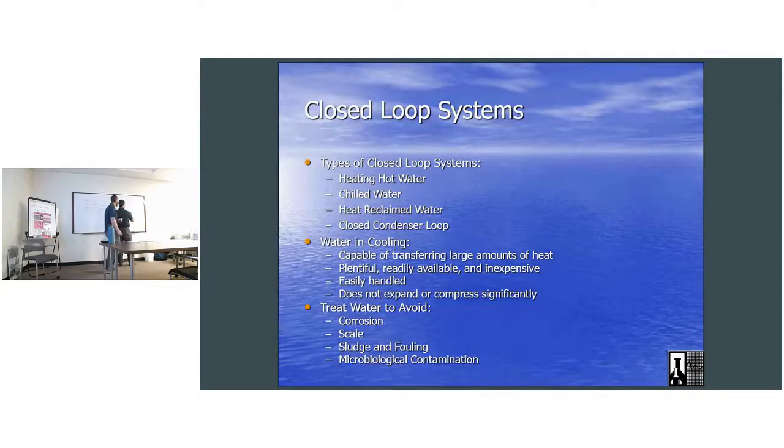The fun ones are the ones that stick a valve right there in the supply line or return line. They intend for you to decrease flow to force it through from, say, a 4-inch line to a 3/4-inch line at a rate that isn't going to starve your pump. That was a really common way to do it in the 70s, and you will see it on a lot of buildings. And it works. Just don't isolate the valve all the way. Watch your pressures here.